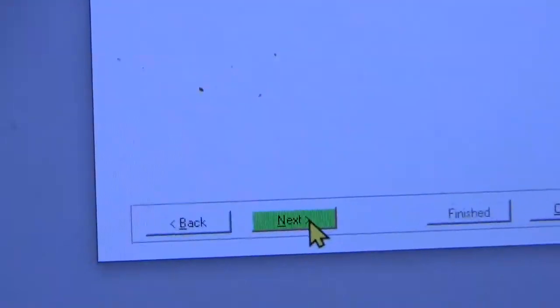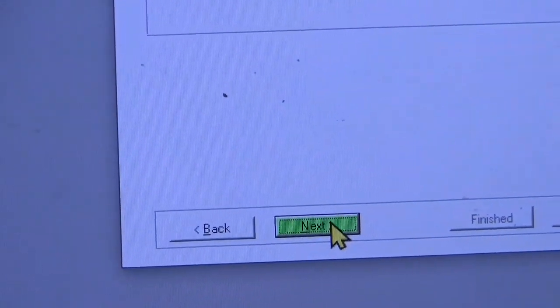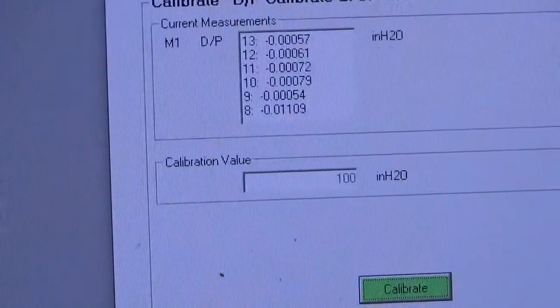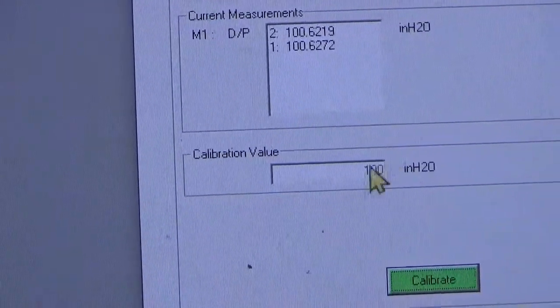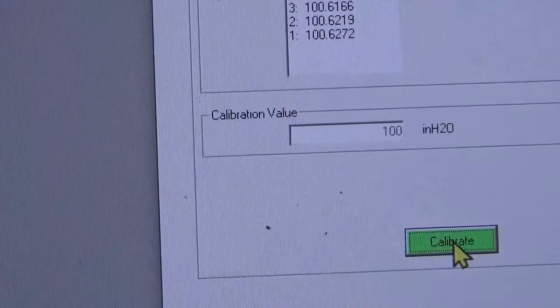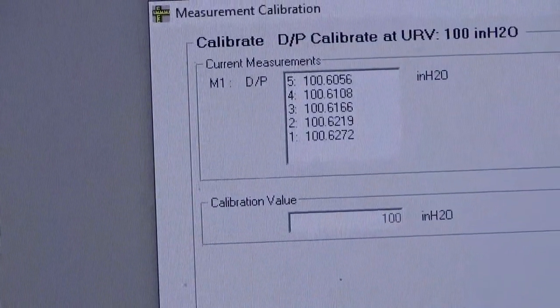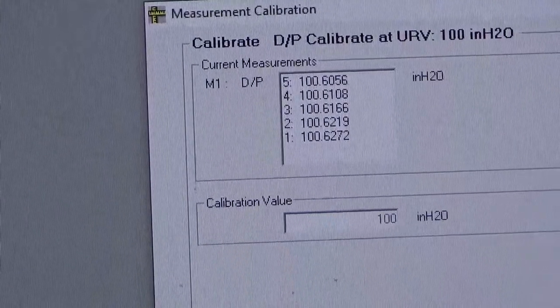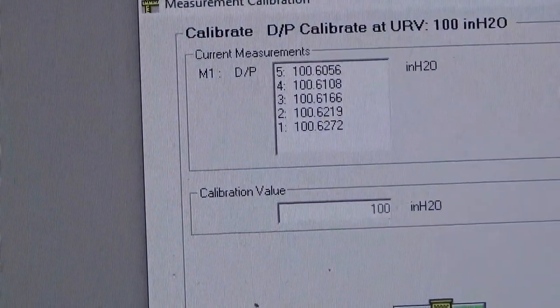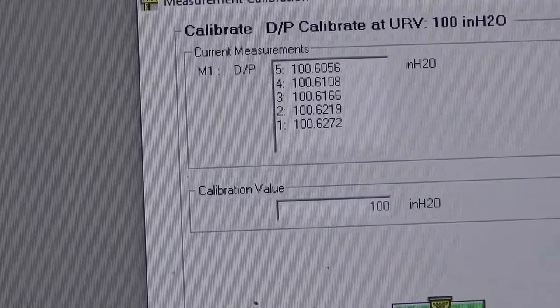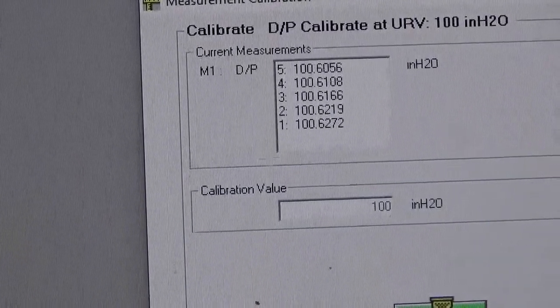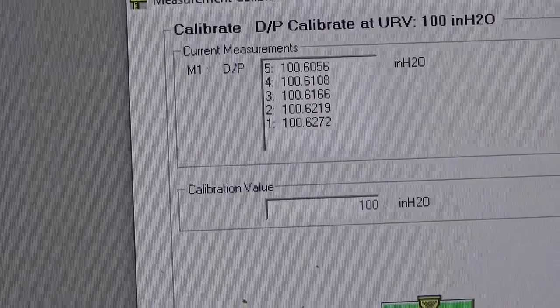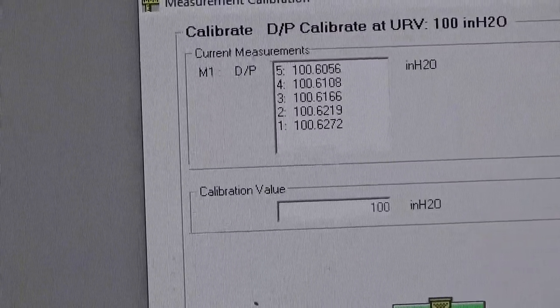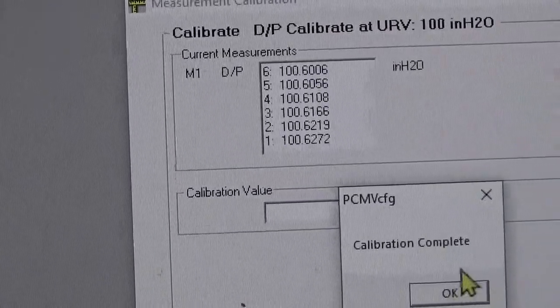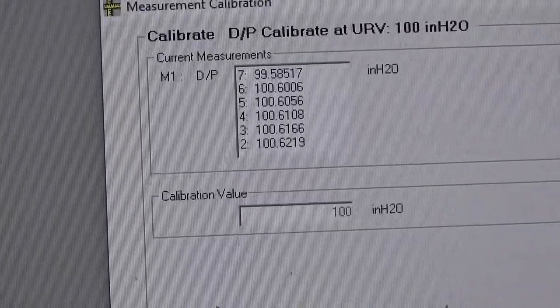and I'm going to hit the next button. It's going to give me the warning again that it's going offline. It's going to tell me here to input 100 inches of water, which I have already done. I'm going to click calibrate. The device will go offline. And when it's finished calibrating, I should get an indication that the calibration is complete, which there it is. I say OK.